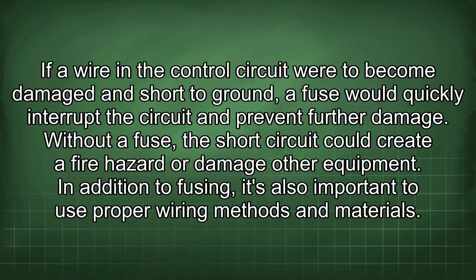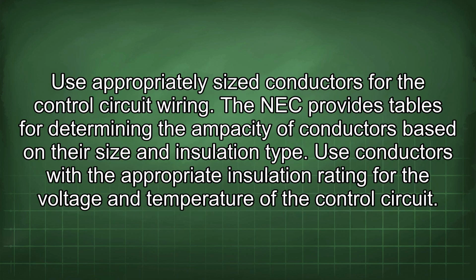Without a fuse, the short circuit could create a fire hazard or damage other equipment. In addition to fusing, it's also important to use proper wiring methods and materials. Use appropriately sized conductors for the control circuit wiring. The NEC provides tables for determining the ampacity of conductors based on their size and insulation type. Use conductors with the appropriate insulation rating for the voltage and temperature of the control circuit.